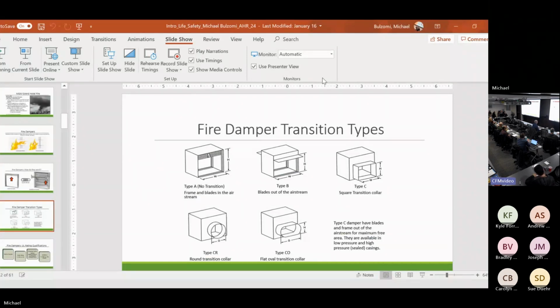But these are our transition types. Type A is no transition. I've got a 12 by 12 duct penetration. I put a 12 by 12 damper. The top of this blade pack is in the airstream. It's eating up pressure drop. It's eating up free area, causing pressure drop, turbulence, and noise.